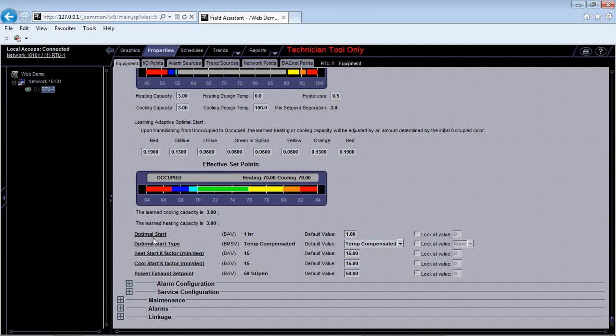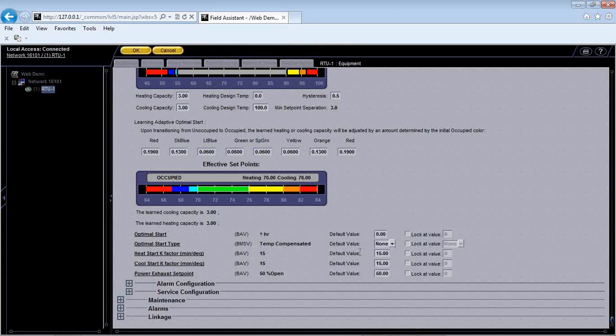If you enable this, it will start the unit as close as it can to the actual start time so that you can get back to the space temperature by the time you go into occupied mode. Okay? It's built in and standard on any unit. If you don't want to use it, you don't have to. You can just put this value at 0 and change this to none. That would be the easiest way to shut it off. I know a lot of times third-party building automation systems have their own optimal start that they use, so you can lock it completely out.